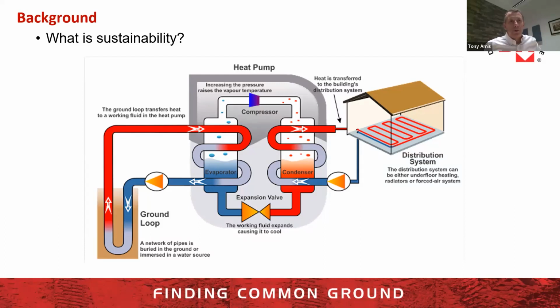So the loop going into the ground, all we're looking to do there is exchange probably 5 to 10 degrees of sort of cool from the building. So as the loop's going to the ground, what we're looking to do is to bring the fluid in those geothermal loops and increase it by somewhere between 5 and 10 degrees Fahrenheit. That then passes through a refrigeration cycle. It's typical of a refrigerator in everybody's home.